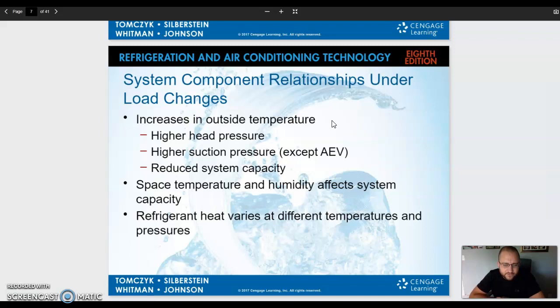So your system is no different. Your system has running pressures and it has standing pressure. Standing pressure is when the system's off, the compressor's not running, there's no low side or high side, it's just basically a container of refrigerant. So if you go up to a system that's not running and put your gauges on it, they should go to standing pressure for whatever temperature it is outside. That can vary a little bit, but if it's a 90-degree day, it should go to a 90-degree saturation temp and whatever pressure that is.